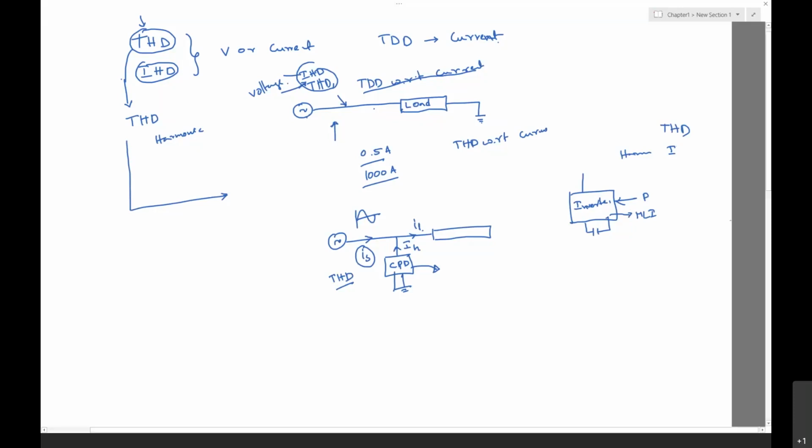In that case, we can go for a THD or the individual harmonic. Even for current quality improvement devices like custom power devices, THD is an appropriate method to know the performance of your custom power devices, and whether the source current quality is improved.